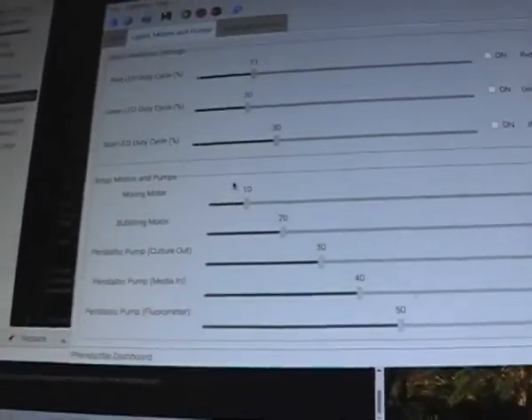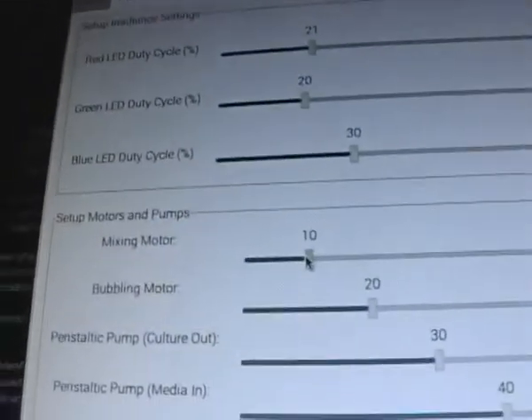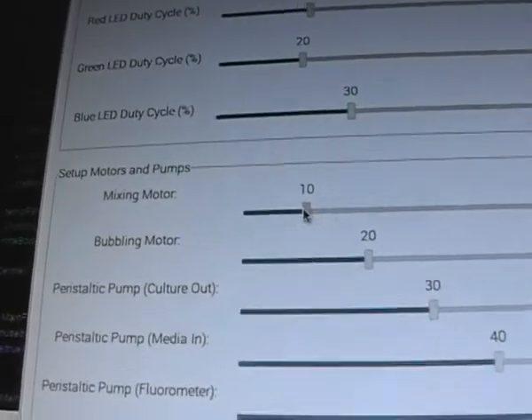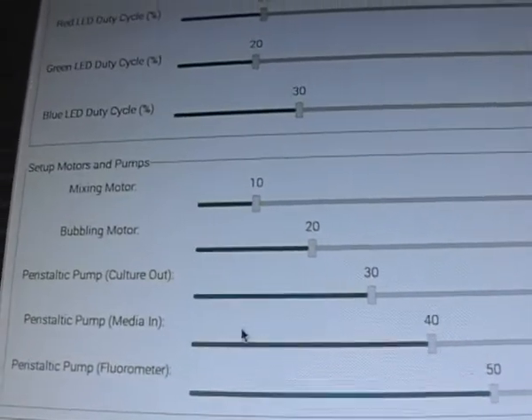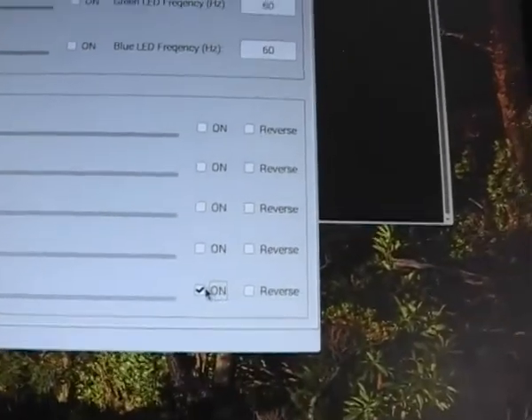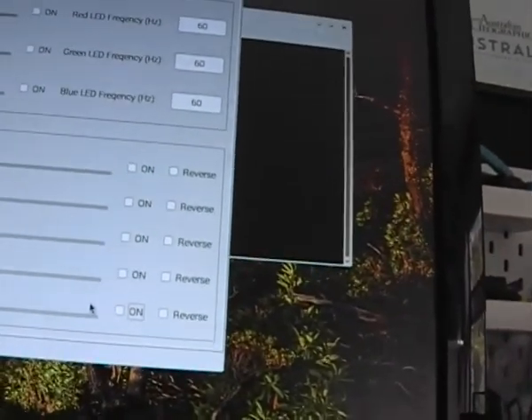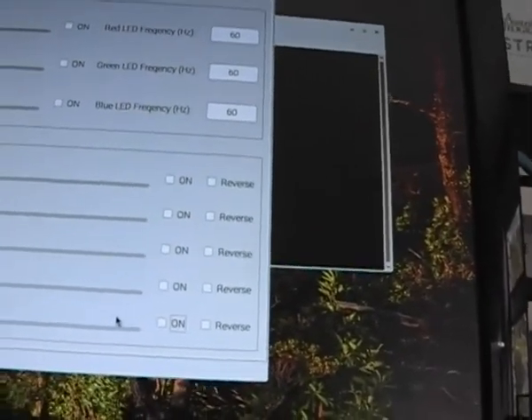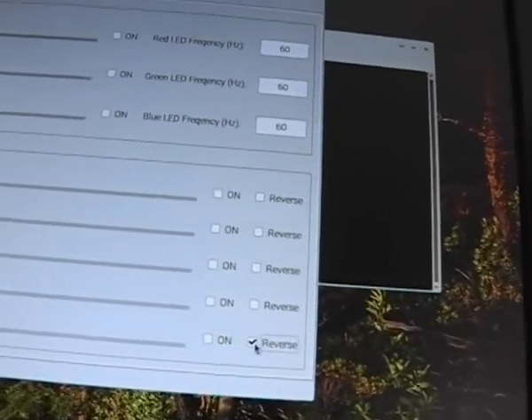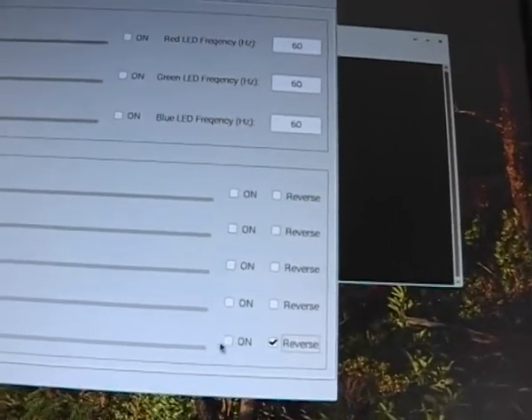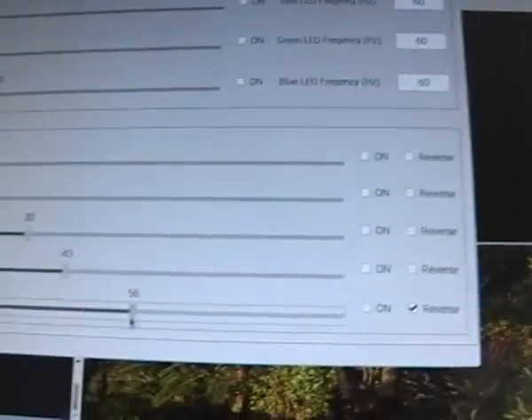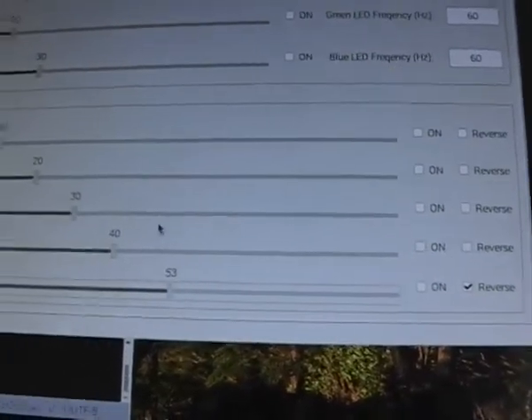And then we have down the bottom here mixing controls: bubbling motor, peristaltic pump, culture in, whatever. All these kinds of things, you can turn them on, you can also reverse them, because a lot of the motors actually have polarities that are switched, which is kind of annoying. But the reverse function will just allow you to say, yeah, I want that motor to run in reverse, and then just set the value of whatever you want the motor to run at.